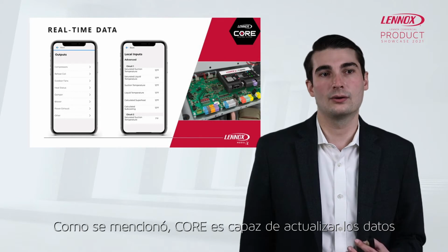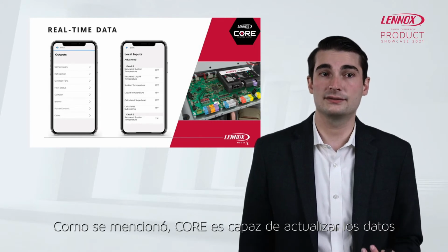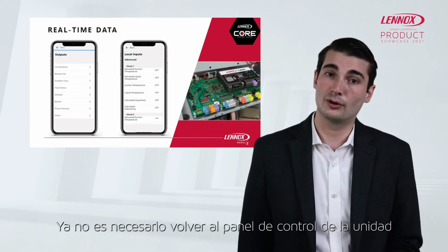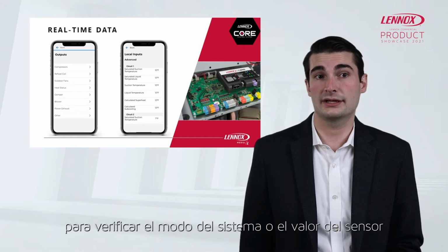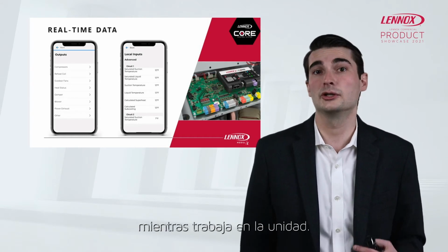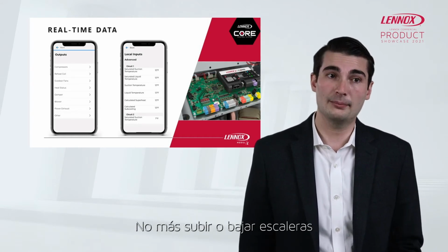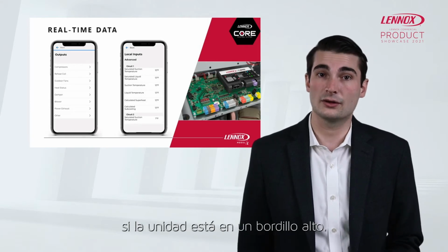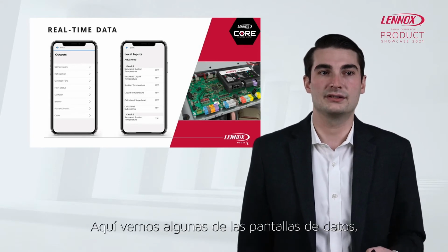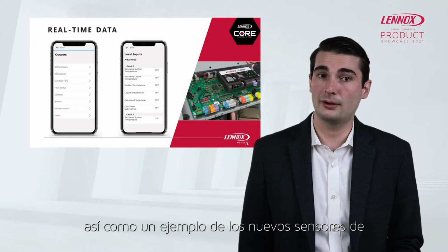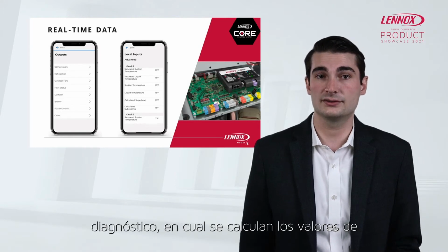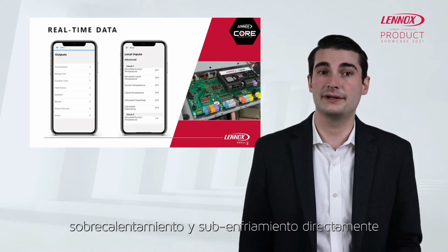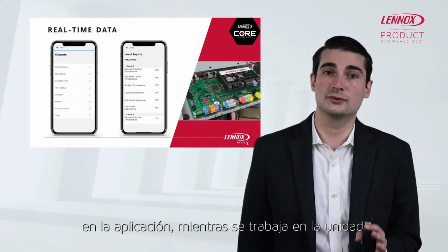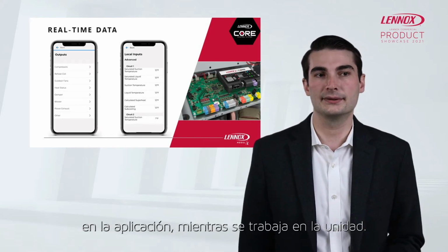As mentioned, Core is capable of updating data to the app in real time. No more returning to the control panel of the unit to check a system mode or a sensor value while you're working on the unit. No more going up or down ladders if the unit is on a tall curb. Here we see some of the data screens, as well as an example output of the brand new diagnostic sensors and calculated superheat and subcooling values available directly on the app while you're working on a unit.